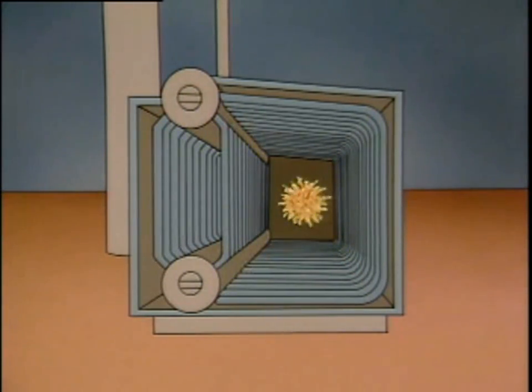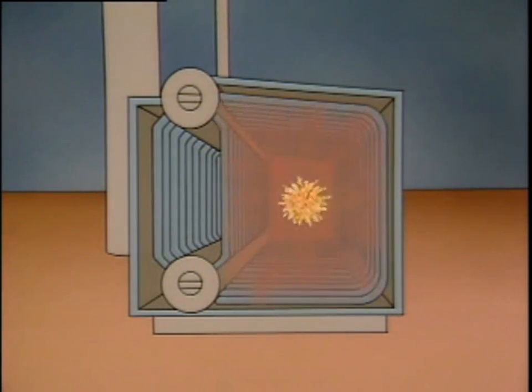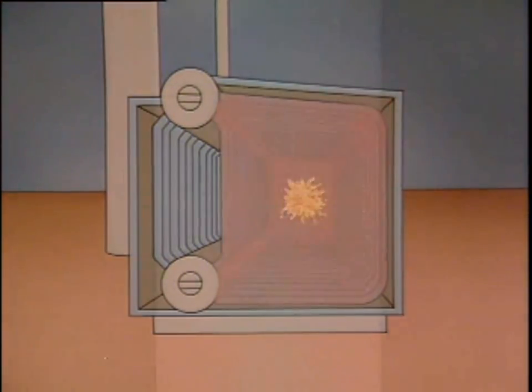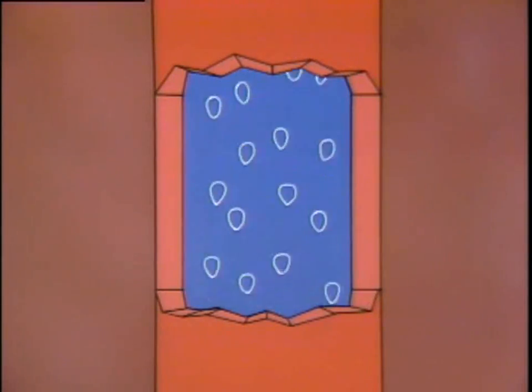The burning fuel also produces combustion gases. As these hot gases pass through the boiler, they transfer heat to the tubes as well — this is convection heat transfer. As the outer surfaces of the tubes absorb heat, conduction heat transfer occurs. Heat is transferred from the outer surface to the cooler inner surface, then from the inner surface to the water flowing through the tube. Convection heat transfer also occurs as the warmer water mixes with cooler water. When enough heat has been transferred to raise the water temperature to the boiling point, steam is produced.